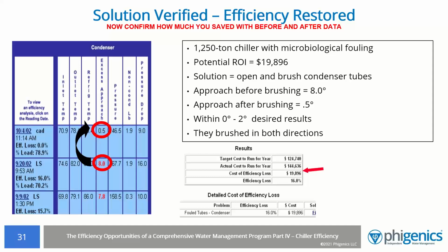So after the initial brushing, the new data showed that there was still a potential ROI of over $19,000. The vendor was required to come back and brush the tubes in both directions. The new approach after brushing was 0.5 degrees. The efficiency of the chiller was restored, and you are now able to show, with data, the value of performing the maintenance or repair.